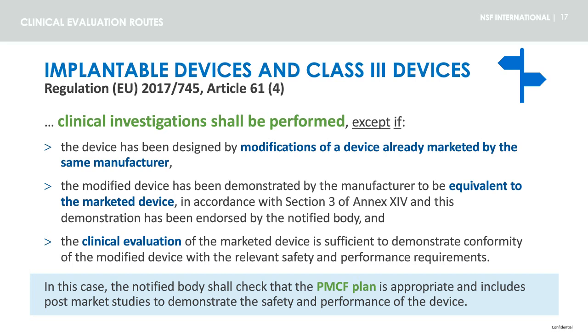Be aware that in this case, the notified body will check if the PMCF plan is appropriate and includes market studies to demonstrate the safety and performance of the device.